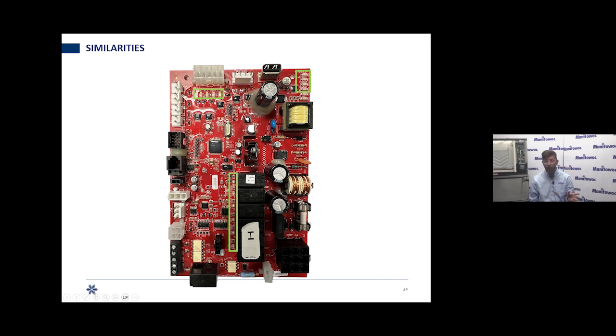Same thing with the wiring, same numbers, I believe same colors. They should be the same colors, but I always go by the wire number, just in case you can't see color, or just in case they were out of blue that day. And up at the top, that's going to be the same for the first four lights. Micro display, they're supposed to be flashing on and off together, one on, one off. Does not matter. What we care about is that they're flashing. You still have a clean and a harvest light. So all of those lights function the same with that one little difference on the water probe.